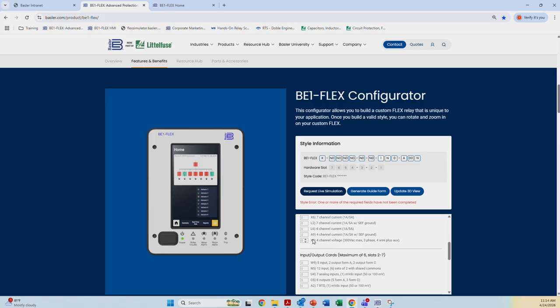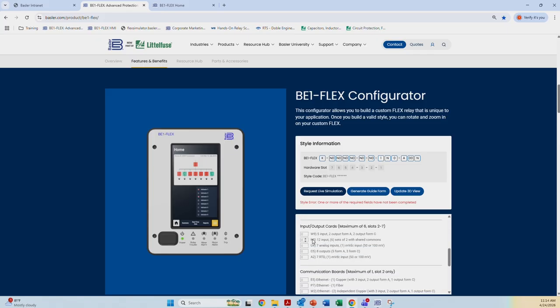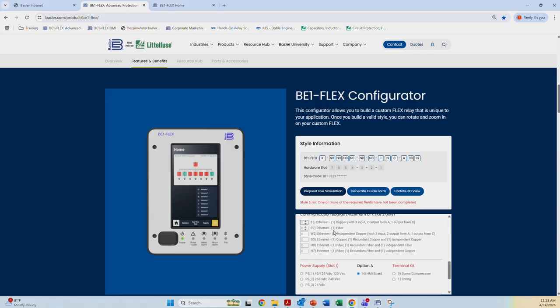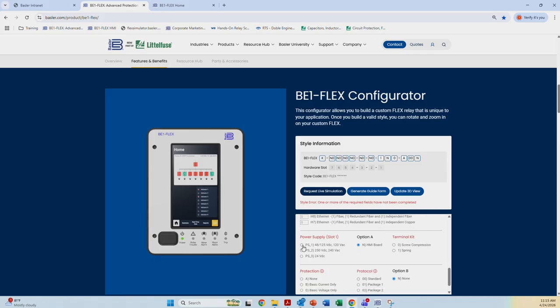We don't need any other analog cards, so we can scroll up to the input-output cards. I would select typically the W9, which gets you 5 inputs and 4 outputs, 2 of them form A, 2 of them form C. We will select an E5 Ethernet card, which is 1 copper Ethernet with an RJ45 connection, along with 3 additional inputs and 3 additional outputs, 2 form A and 1 form C. We will then go down to the power supply and select power supply 1, which is 48 to 125 volts DC and 125 volts AC.